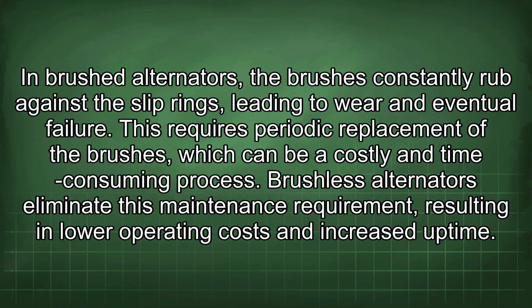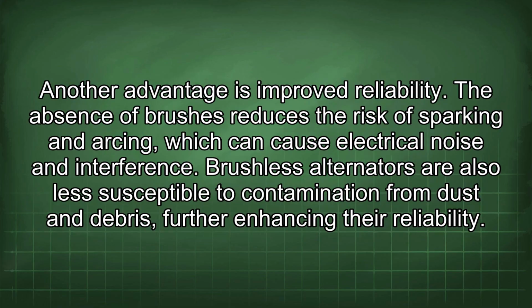In brushed alternators, the brushes constantly rub against the slip rings, leading to wear and eventual failure. This requires periodic replacement of the brushes, which can be a costly and time-consuming process. Brushless alternators eliminate this maintenance requirement, resulting in lower operating costs and increased uptime. Another advantage is improved reliability.